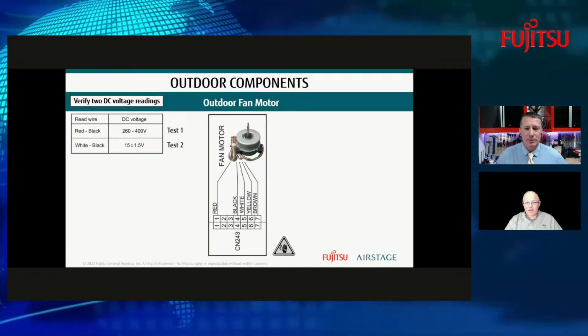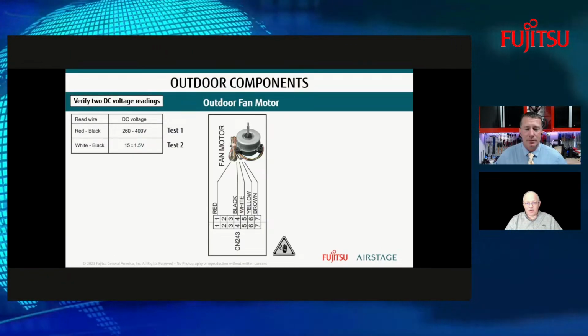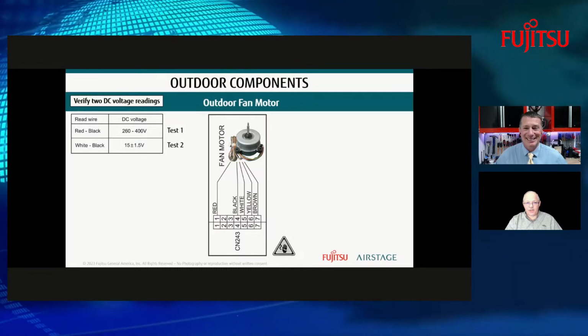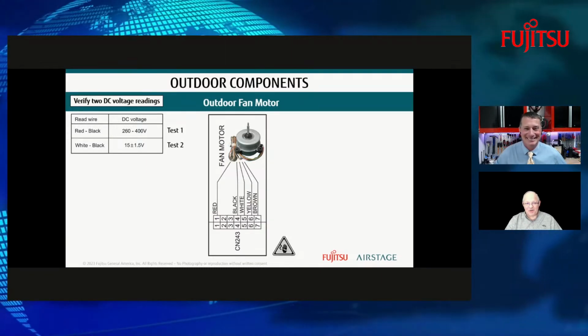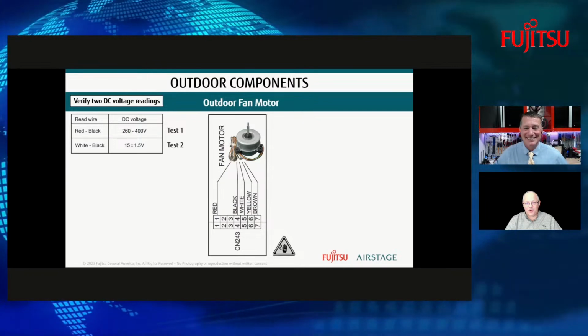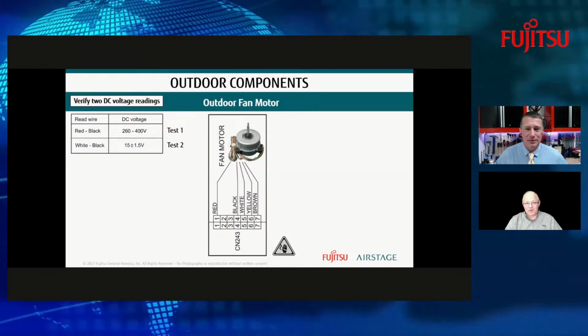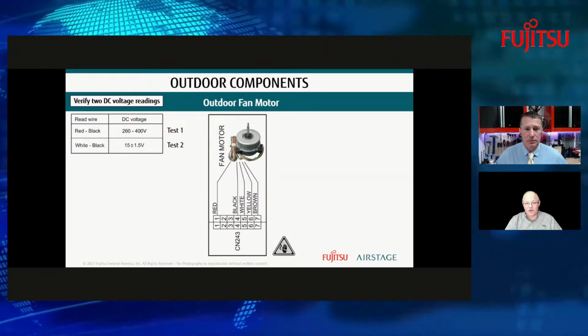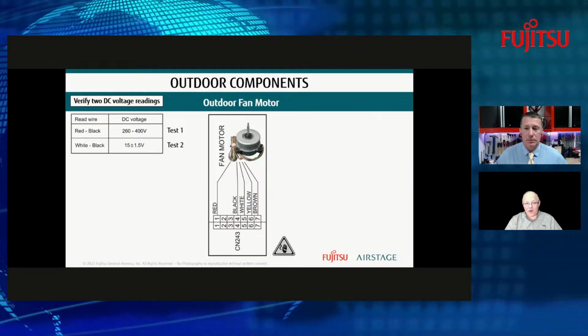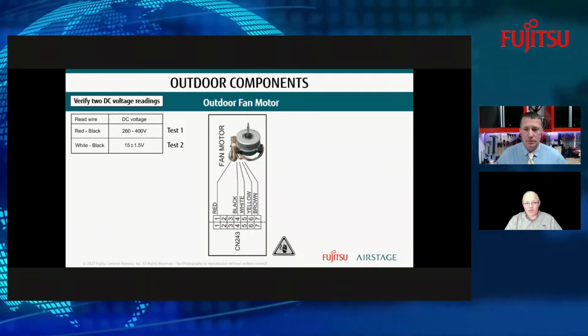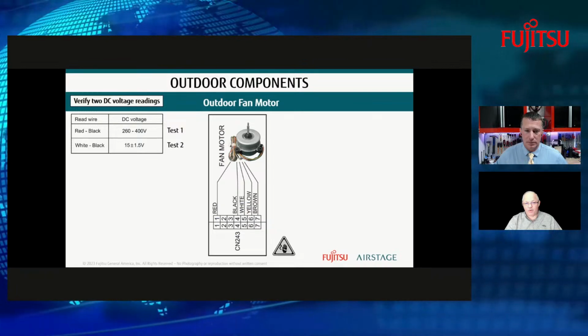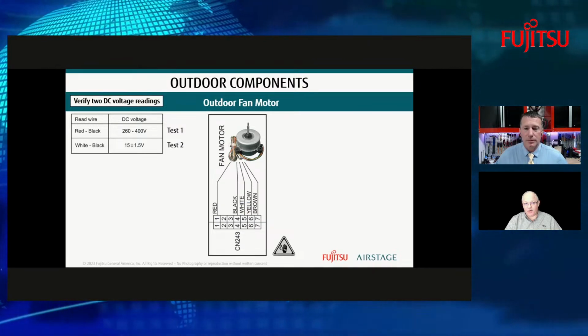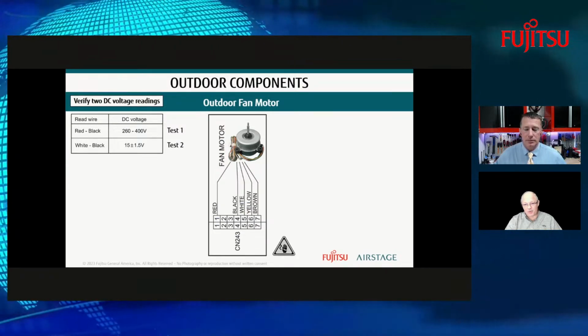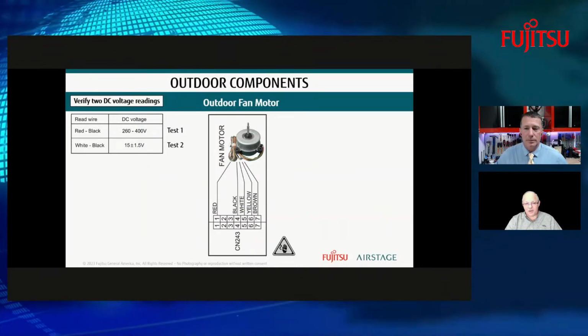So when we're talking about the outdoor fan motors, a lot of times guys ask, well, what's the voltage of it? Well, this is an example of two different voltage readings that have to go to the outdoor fan motor. If you were to check on the red and the black wire, you would see anything from 260 to 400 volts DC on this particular model. Now, voltage can change depending on the model and the size of the unit.